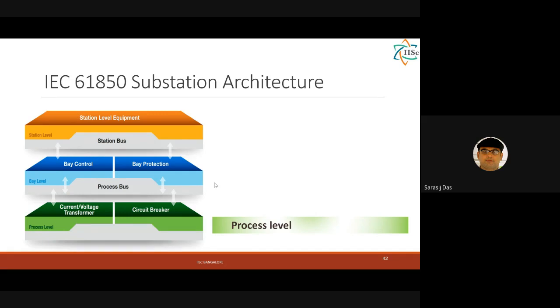So all individual circuit breakers, current transformers, and voltage transformers form the process level. Now, bay level: what is a bay? A bay can be basically a feeder, or a portion of a transmission line, right? Whatever devices are connected to that particular feeder or transmission line are grouped into a bay. Suppose on that line you have three CTs, three VTs, and one transformer. All these are grouped into a bay. We call this a bay. So a bay contains several individual equipments.